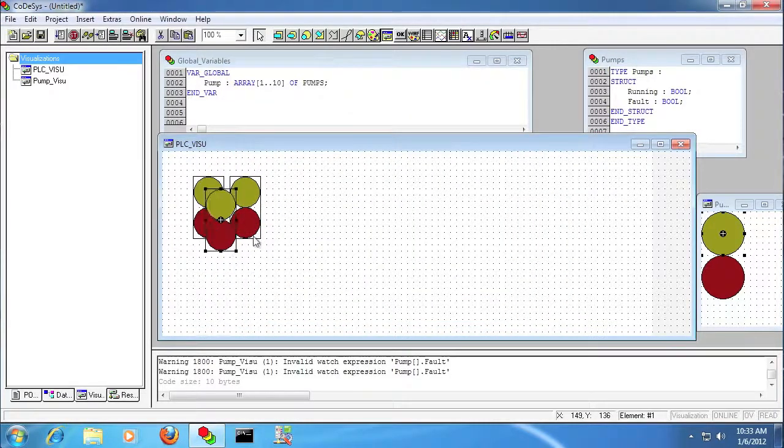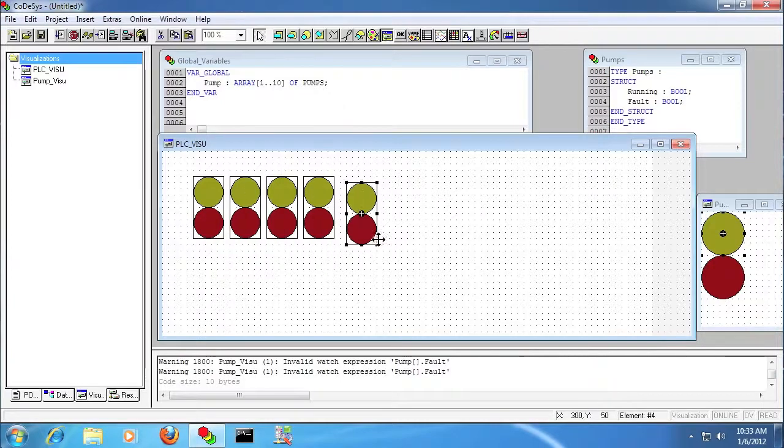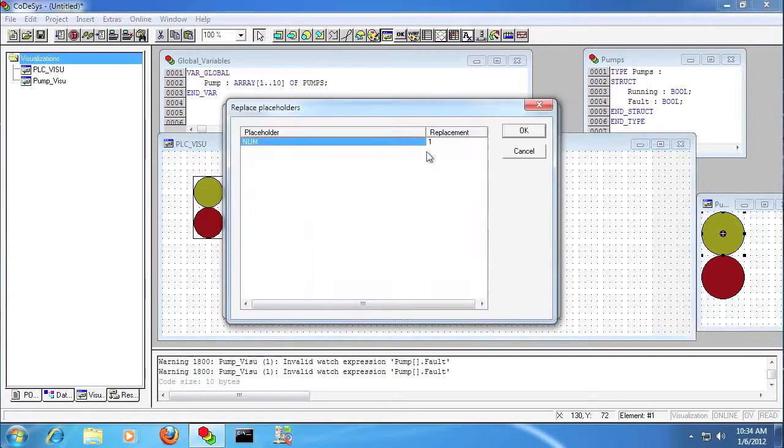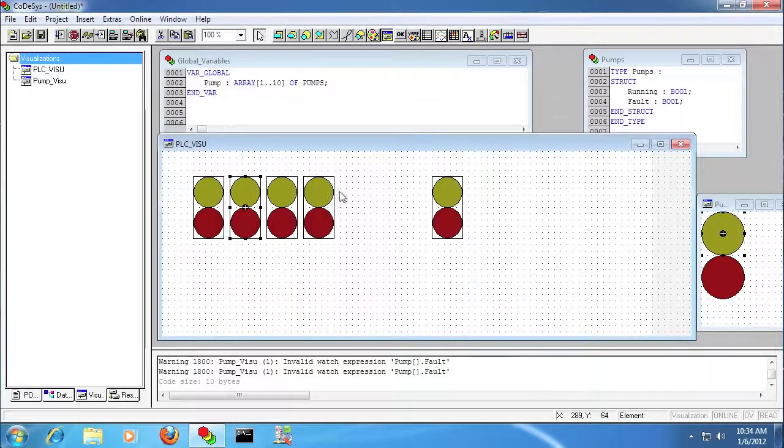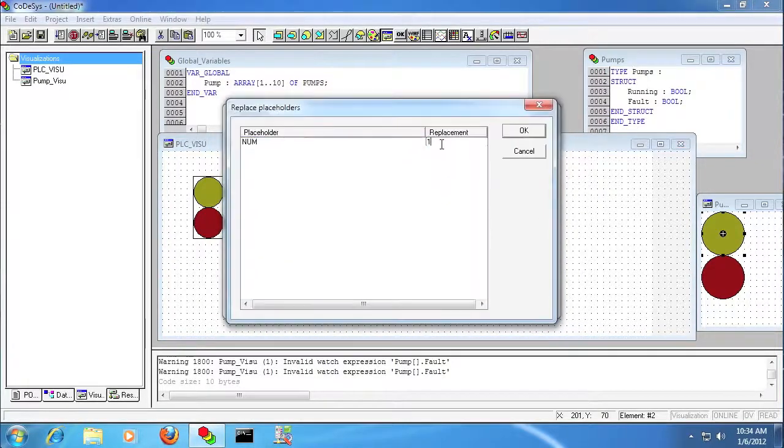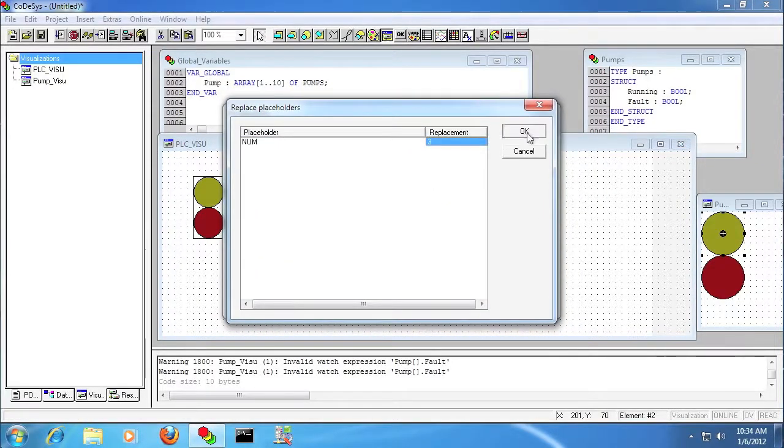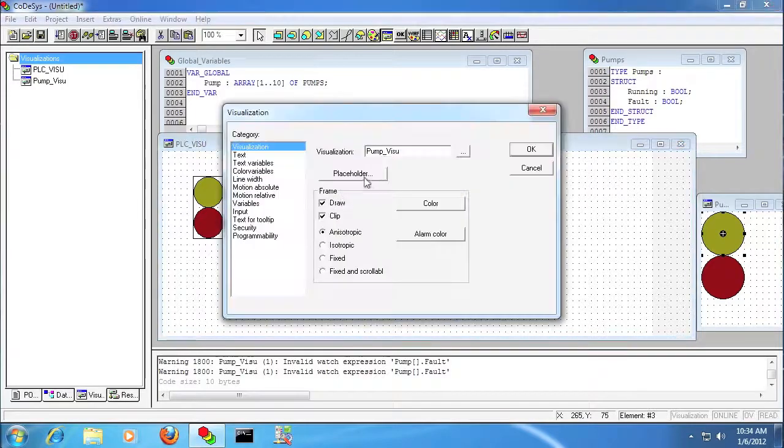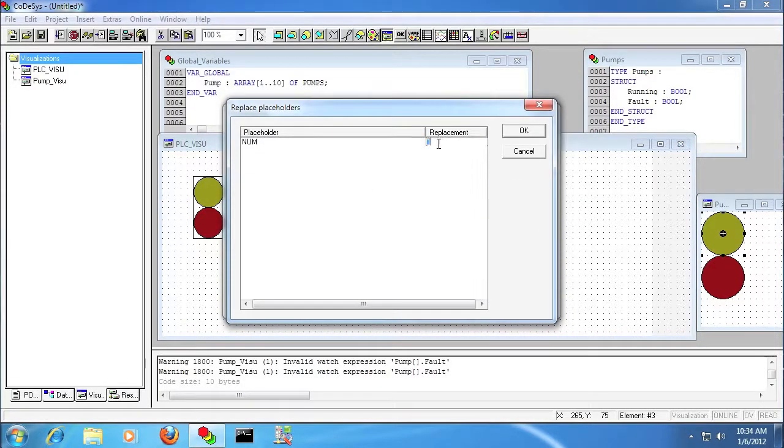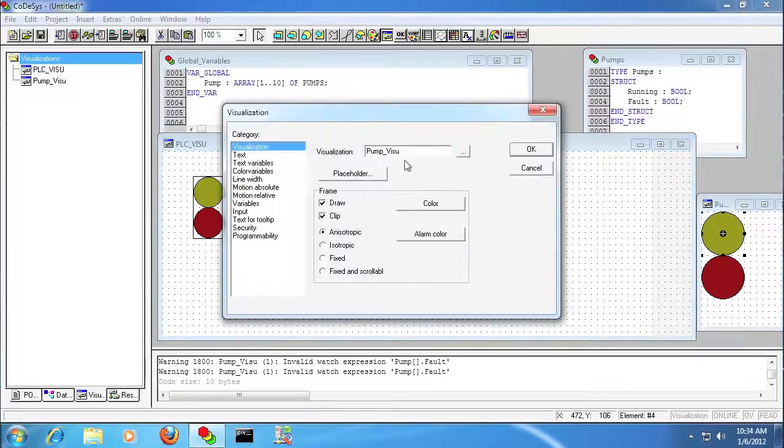I'm just going to cut and paste a couple more of these just to show how this works. And then I'm going to go into each one and change those to reference the other pumps. And so anywhere we use that dollar sign num, it's being replaced with whatever we put in that replacement field. So I've got the first four, and then I'll just do the tenth one just to show that they all are in fact working.